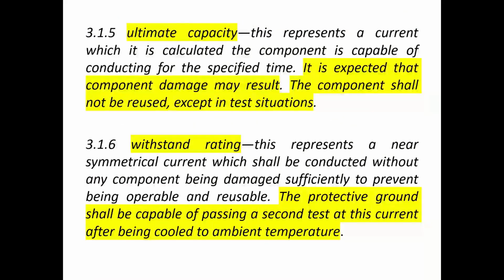So here's the definitions in ASTM F855. Ultimate capacity: it is expected that component damage may result. Wonder why? You're having an explosion there, pal. The component shall not be reused except in test situations, if there's anything left. The withstand rating: the protective ground shall be capable of passing a second test at the current after being cooled to ambient temperature. So at least you have some kind of chance here. And I always use the withstand rating.